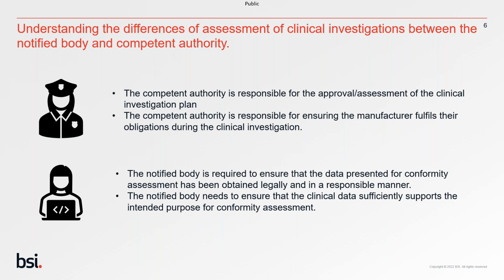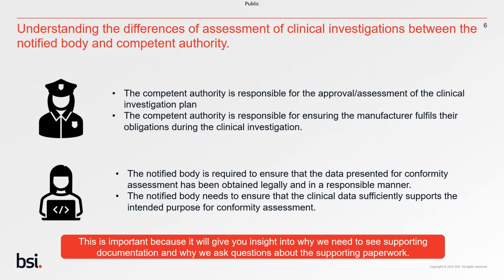The notified body needs to ensure that the clinical data sufficiently supports the intended purpose for the conformity assessment. And as I said, it's important to clarify this, because what we are looking for in terms of the clinical investigation design and the results of that clinical investigation is really the justification as to why that method was chosen and an understanding of what has happened historically.